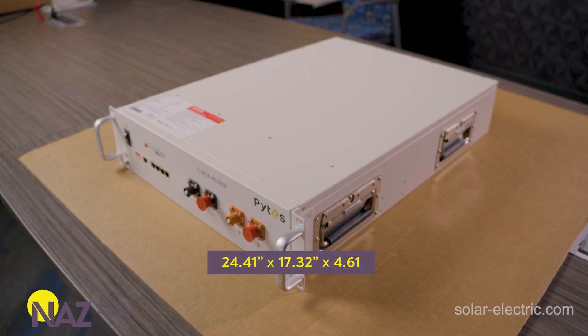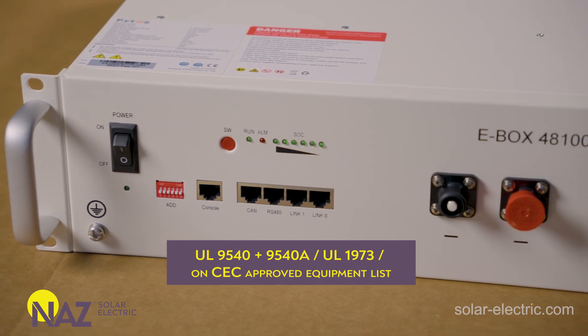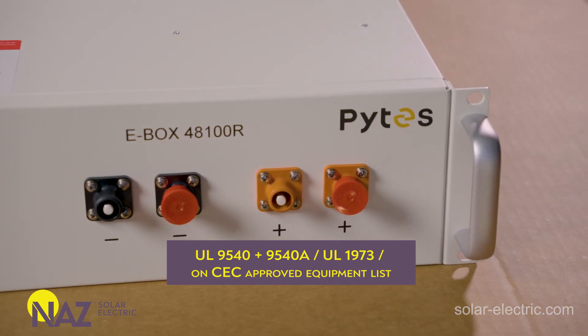In terms of physical size, the Pytes battery is about 24 and a half inches long, roughly 17 and a quarter inches wide, and only about four and a half inches tall — a very compact, slim form factor with that server rack design. Each battery weighs about 113 pounds. Pytes backs their batteries with a 10-year manufacturer warranty. The Pytes batteries also have UL9540, UL9540A, and UL1973 certifications, and they're also on the CEC — the California Energy Commission's approved equipment list.